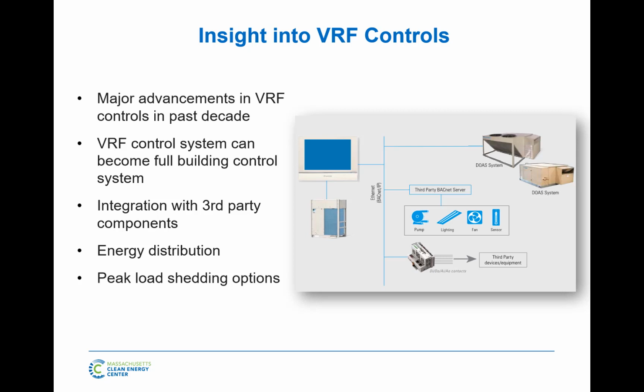So now the VRF people have built their own little touchscreen that's a plug and play central controller. You put that on the wall, you wire it to the condensing units, and you're done. From there, you automatically, without demanding graphics, without hiring a controls company, can see and touch all the VRF indoor units, set points, scheduling, room temperatures. You bring internet to it, just an Ethernet cord. Now you can remote in from anywhere, with automatic alerts.